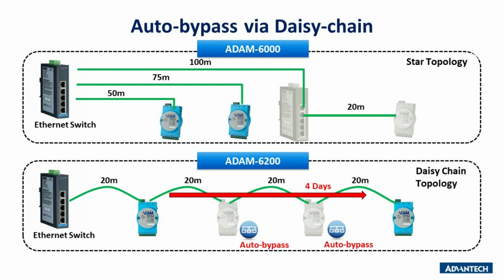And if, let's say, you have some limitation in the LAN ports on site, you can connect directly to your IPC or laptop LAN ports to perform daisy chain. Unlike Adam 6000, you must have a switch to act as your master device and each Adam connects directly to the switch. Also, the data will be lost if either of the Adams fails to operate.